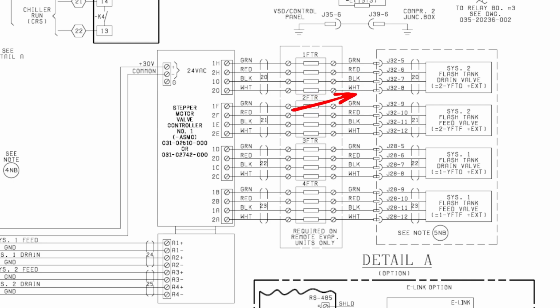If we want to reverse that, we would just reverse our polarity. And we would also step in a reverse direction. So we would go white, black, red, green, white, black, red, green. And we would step counterclockwise, which would open the valve. So counterclockwise on these is opening. Clockwise would be a closing force. But yeah, all these would just tie back directly into that common leg.